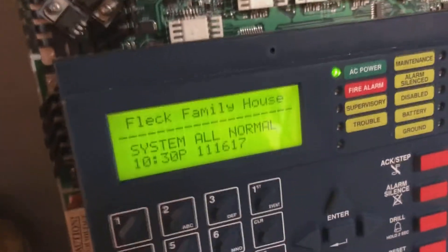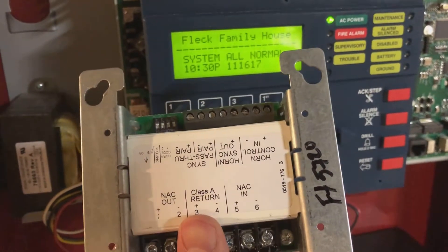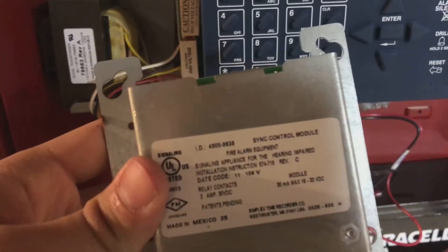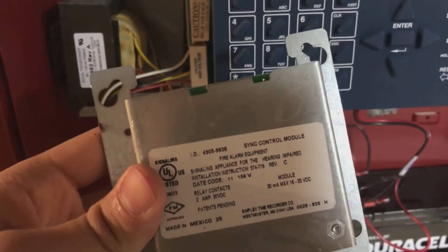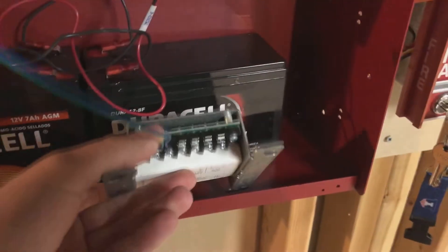Alright, in order to do this properly, because this puts out full wave rectified current and doesn't natively support Simplex sync, we need two different components. For starters, for syncing, we need a Simplex sync module - this one in particular, I believe, has a label on the back, is model number 4905-9938. And this module will allow us to sync, but it won't work properly if we don't have one of these guys.